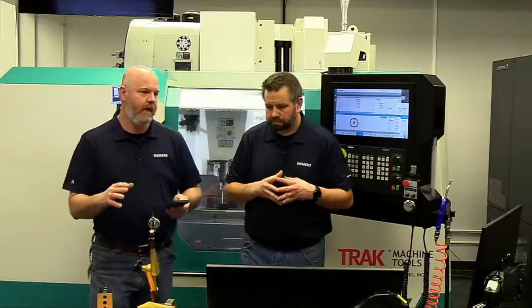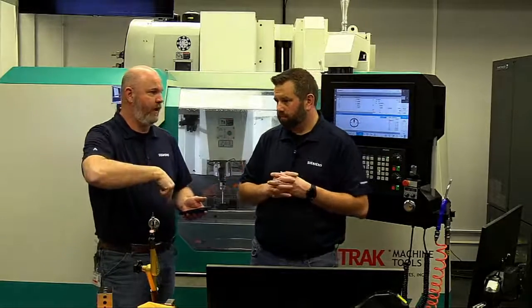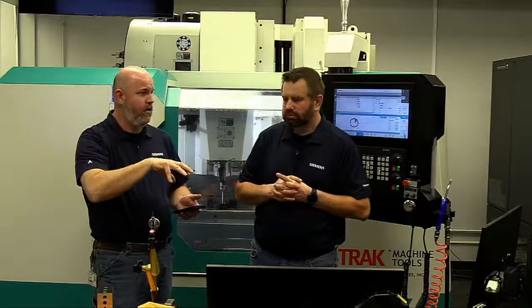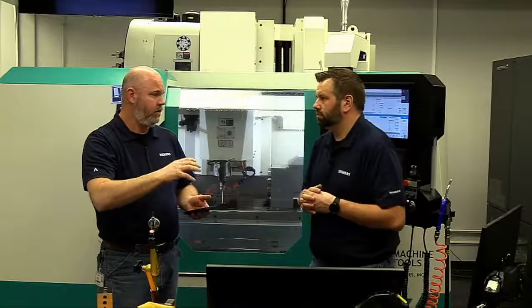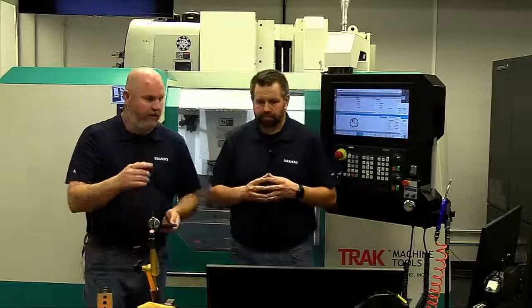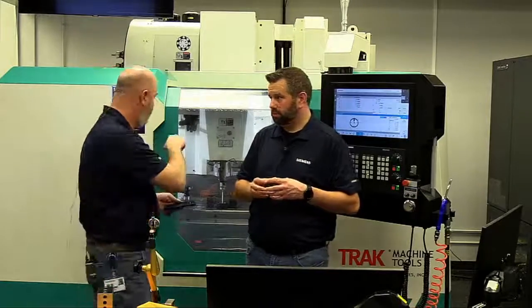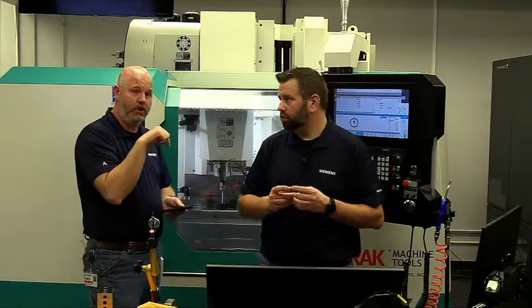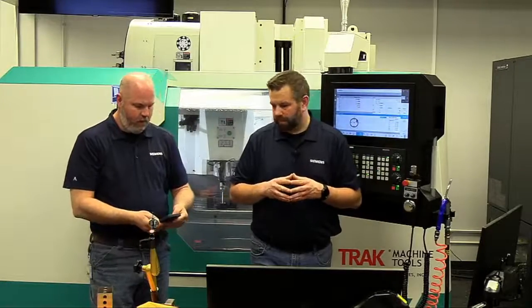Gotcha. So basically you're saying, for his case, if he indicates in the ring gauge and then calibrates, making sure the probe was dead center before he turned on calibration, that'll at least fix it. Correct. Okay, cool. There is another trigger you'll notice. If your machine's set up for that, it'll only ever take one measurement around the ring gauge. If you watch ours, it actually took two. Yep. First one is strictly to find the center of the ring gauge. Second one is to measure all 4 trigger points. Correct. Cool. And then we had one more.